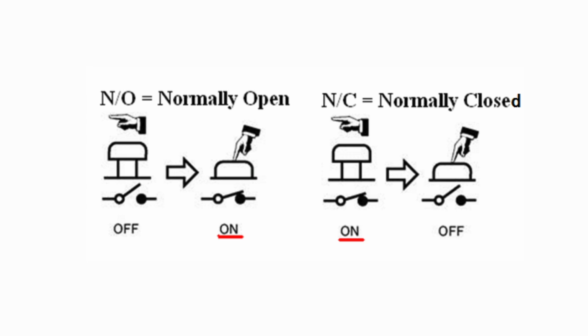A normally closed contact, or NC, closes when its linked input or bit is 0. In other words, if a stop button is 0 or not pressed, the contact closes. When the stop button is true or pressed, it opens and it stops the rung. This might feel backwards at first, but it makes sense if you think in terms of electrical wiring. A normally closed contact passes current until the button is pressed.